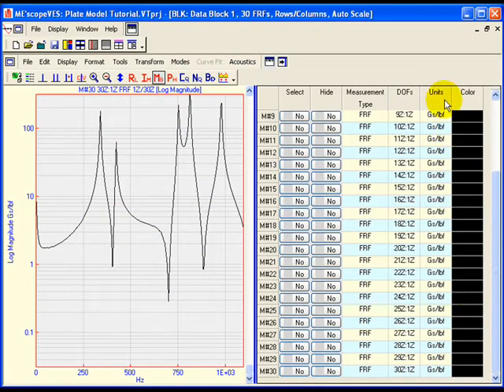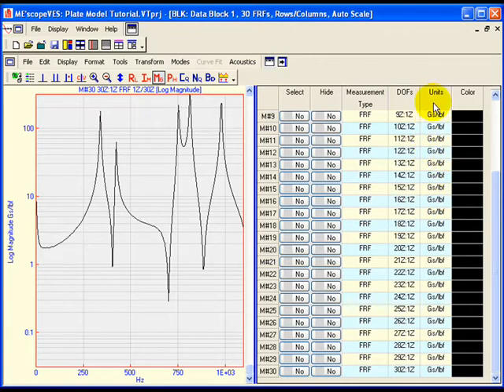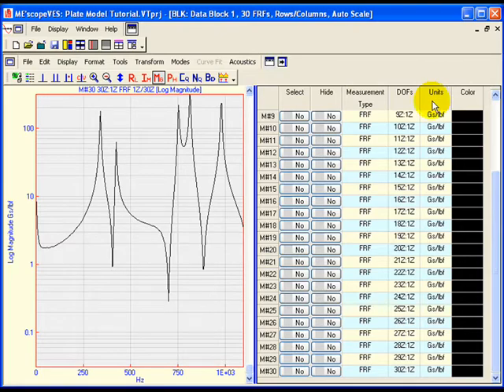Notice also that all of the measurements have the same units, in this case Gs per pound. The FRF units indicate that the response, or output, was measured with an accelerometer in Gs, and the excitation, or input, was measured with a force gauge, or load cell, in pounds.